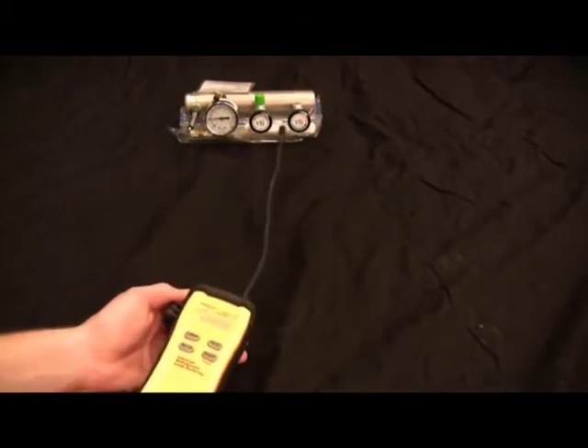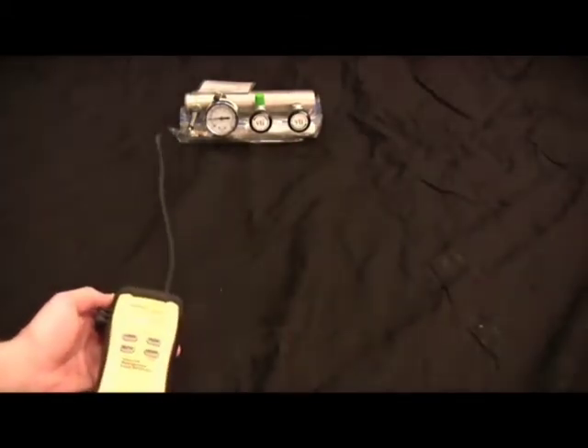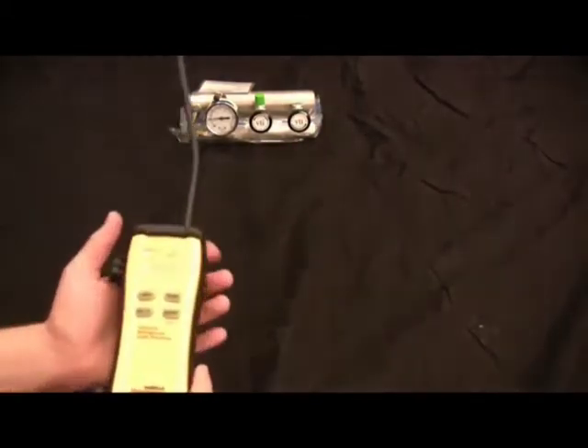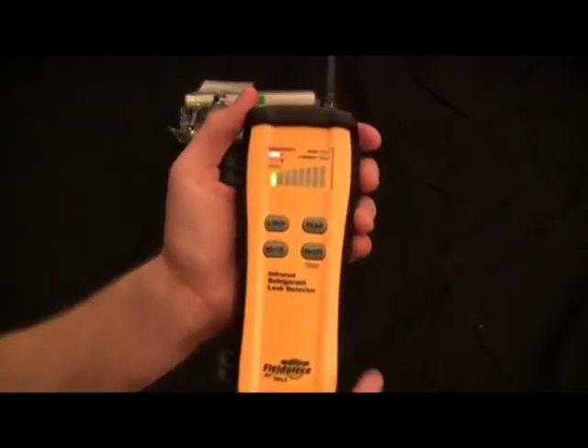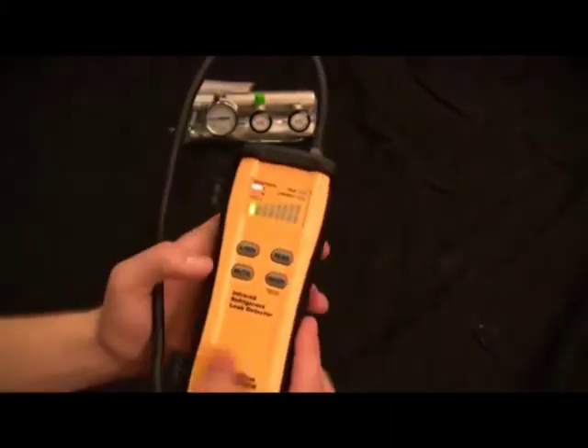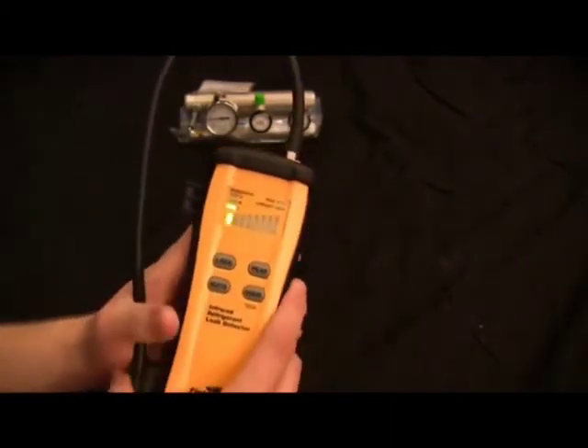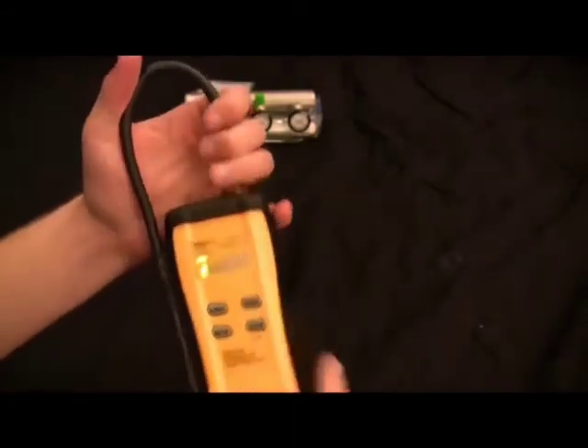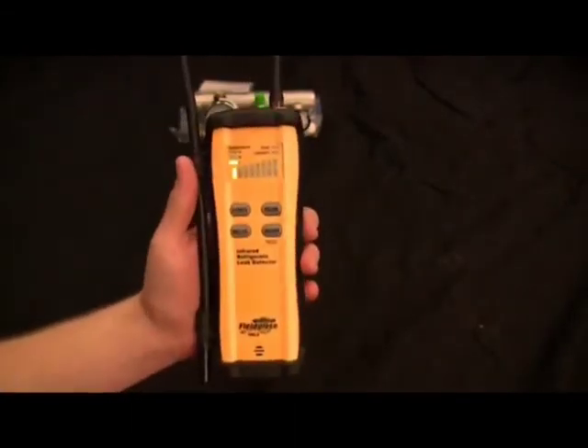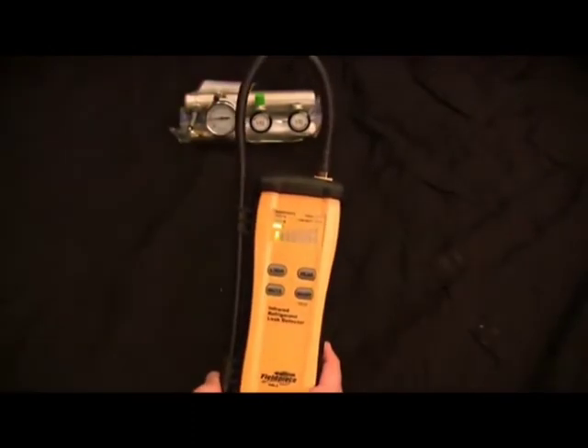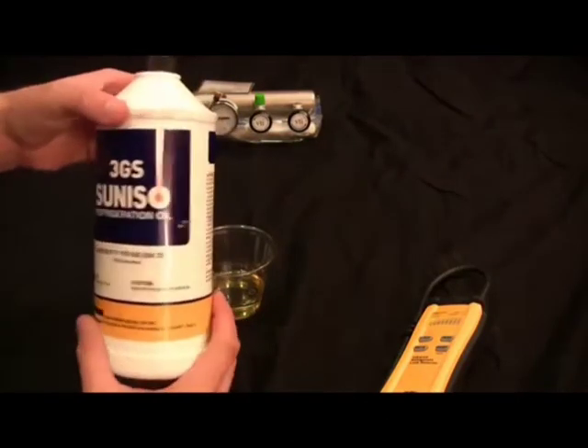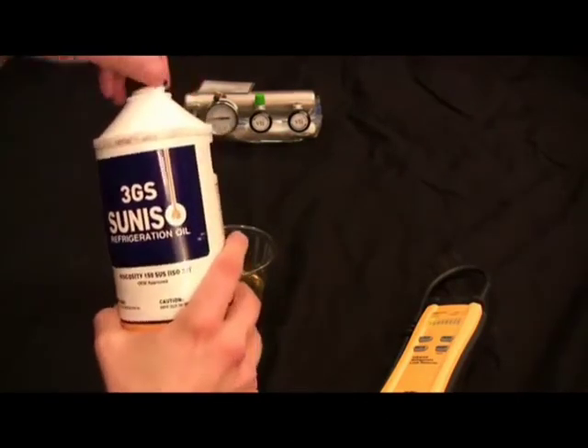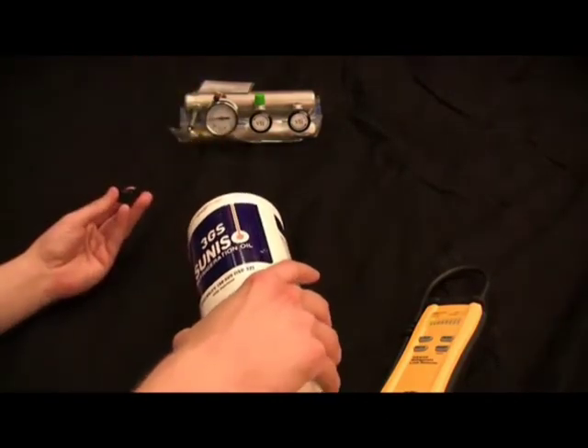And first I'm going to put it into high sensitivity just to give it the worst case scenario. And put it right down that level. Now obviously I'm not going to stick it in, but it's not going off on any of those fumes. I can actually smell them. Now let's put it into turbo mode. Put it into turbo mode. You can see that the light is fluttering. And it's still not going to go off on that refrigerant oil. So there is the SRL-2.